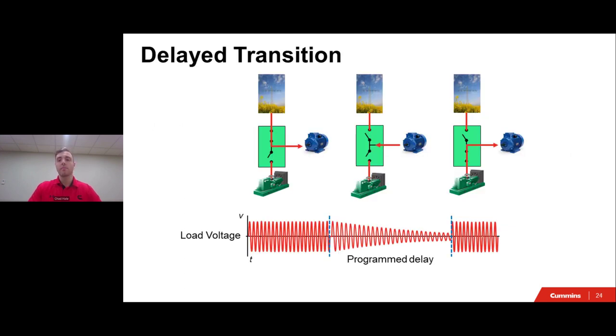Next up, we have our time delayed transitions, which is once again part of that open transition style. So here we can see the operating sequence of a program transition transfer switch. Notice that the load voltage decays slowly once the inductive loads have been disconnected from the power source. And that decay there is in the middle. You can see the little squiggly lines going down. The program transition transfer has a delay that allows the load generated voltage to decay to a safe voltage. It is important to understand that the transfer switch does not measure the residual voltage. It only creates a predetermined pause between switching to allow the residual voltage to decay.